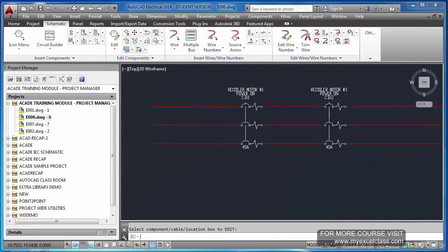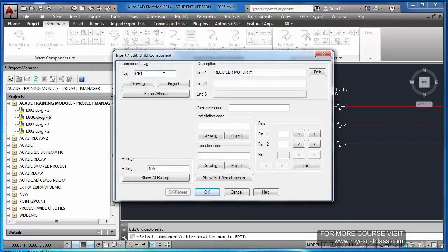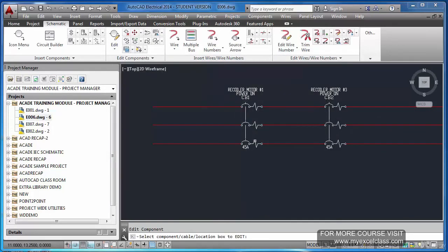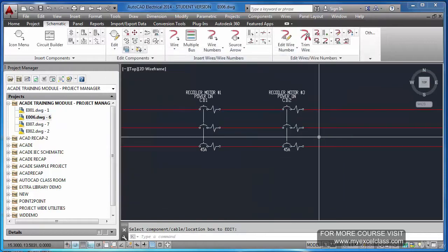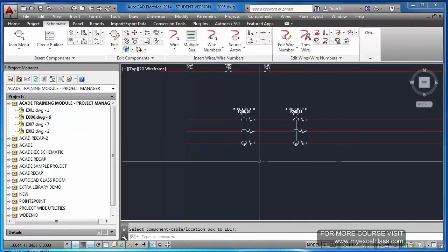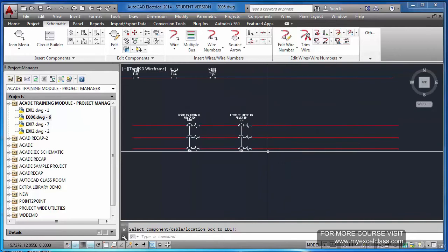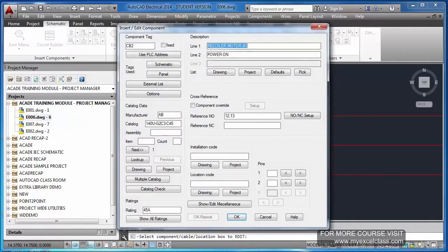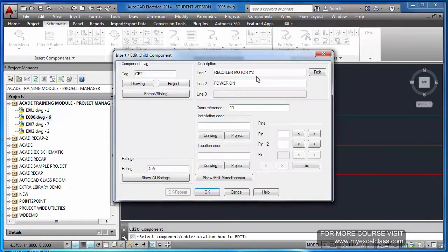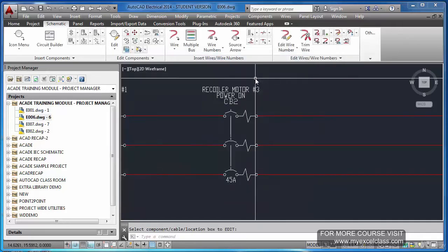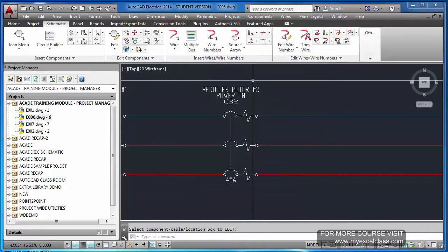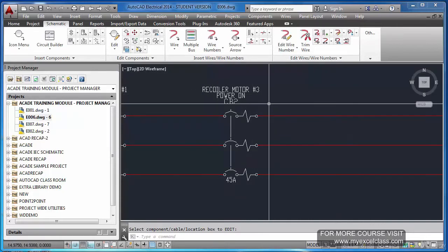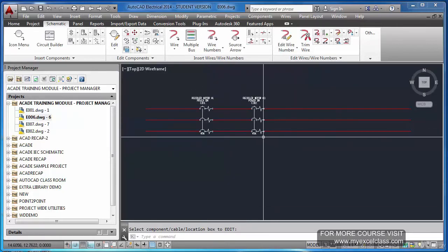But in this case what we have done, we have updated. When we edited a component, we have used the update option. So it is always necessary to do the update command while copying or editing a component. Otherwise one pole will be with a particular value and the other one with something else. So if you extract the details into Excel or some other, and maybe if you try to put this data into the drawing, it won't match.